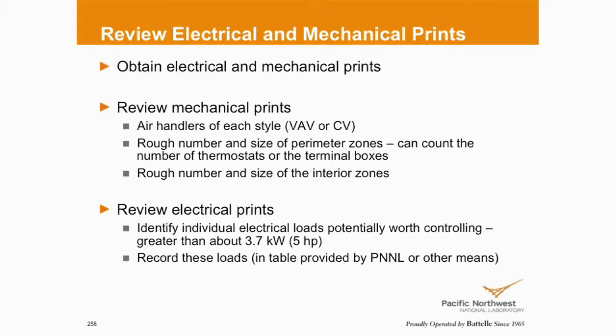Electrical prints, anything greater than 3.7 kW, 5 horsepower, that might be an opportunity to identify on the electrical print. There's a lot of things on electrical prints. Ceiling radiant heaters. I can't believe how many buildings put them in. They're legacy, but some of those things are big energy hogs. And they're out of sight, out of mind, until you walk around with an infrared camera and you go, wow, look at that bright red. Because you don't know they're there. Heat trace. Heat trace on gutters. Heat trace for cooling tower, domestic hot water lines. Those, should I turn them off?